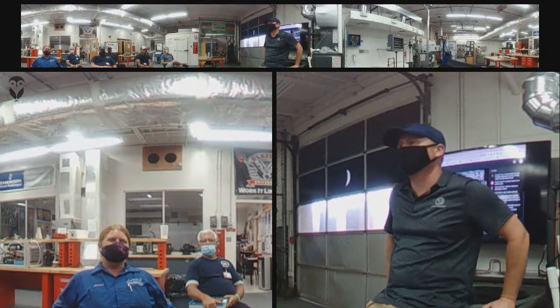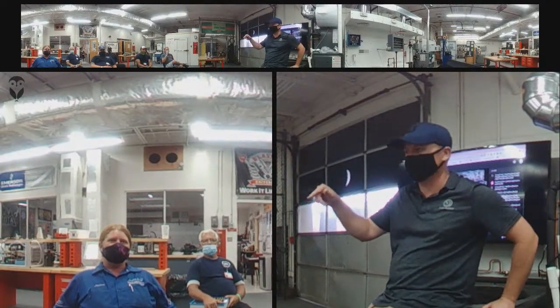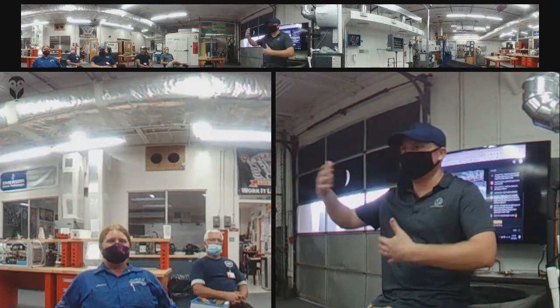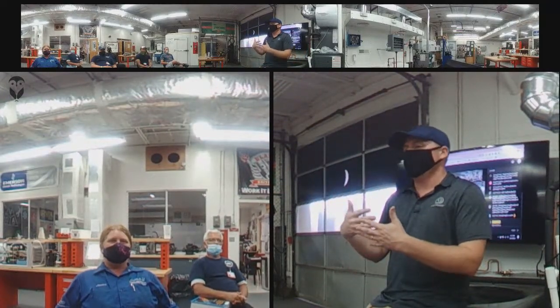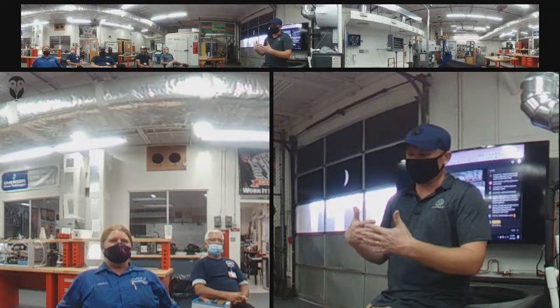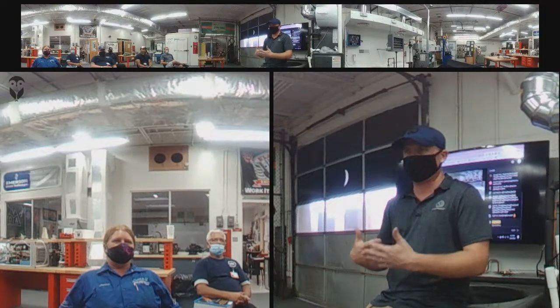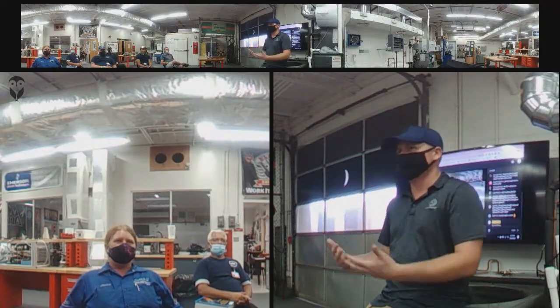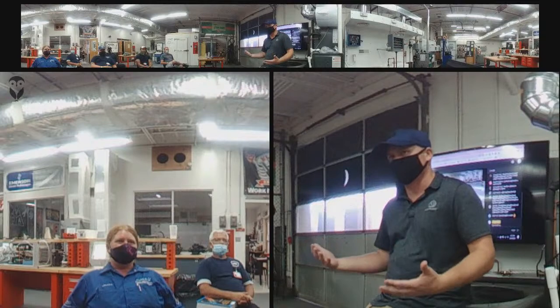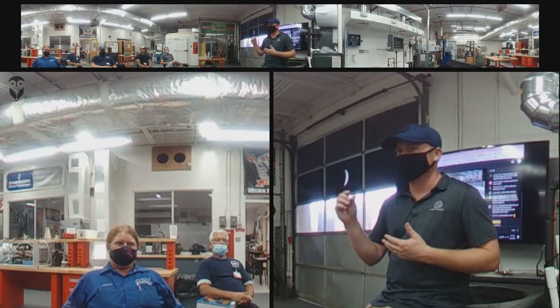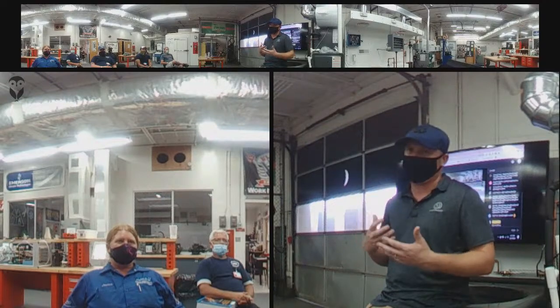And what we find often, and we talked about this a couple classes back too, and obviously we're not at that part yet, but we keep jumping ahead and then dialing it back, is that especially in residential, a lot of technicians get away with not getting the joints hot enough, because in residential the connections we're making aren't nearly as stressed as in other parts of the industry. So we get away with making connections that maybe we never got hot enough in the first place.